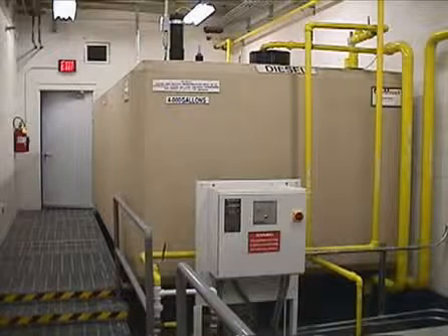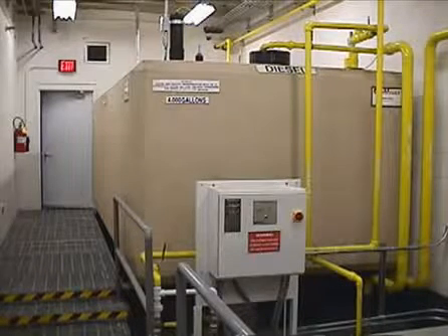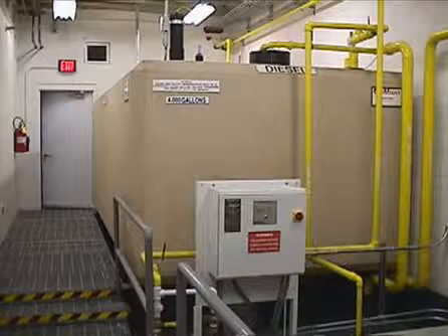The tank rooms may be considered a hazardous electrical area by the fire marshal or insurance carrier. The fuel system equipment needs to be rated for this classification, as well as lighting, ventilation, and all other electrical devices.